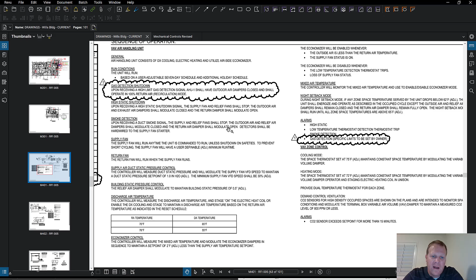But somebody wrote some control logic that says when you receive an input from the smoke detector, then the supply and relief fan shall stop. The outdoor air relief dampers shall close. The return air damper shall modulate to open. Detectors shall be hardwired to the supply fan starter.